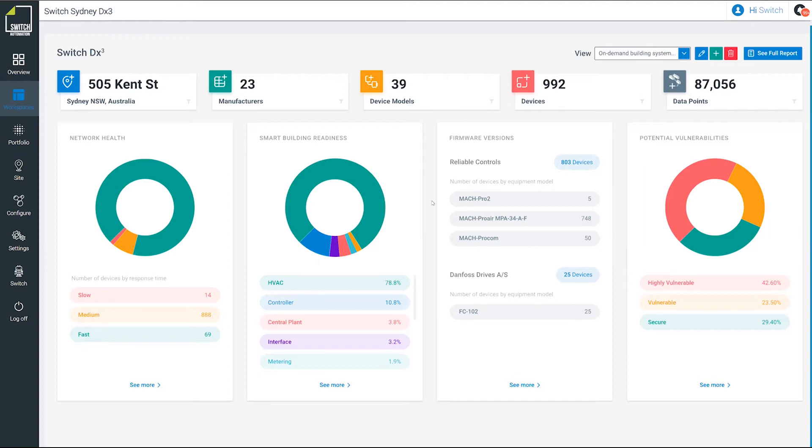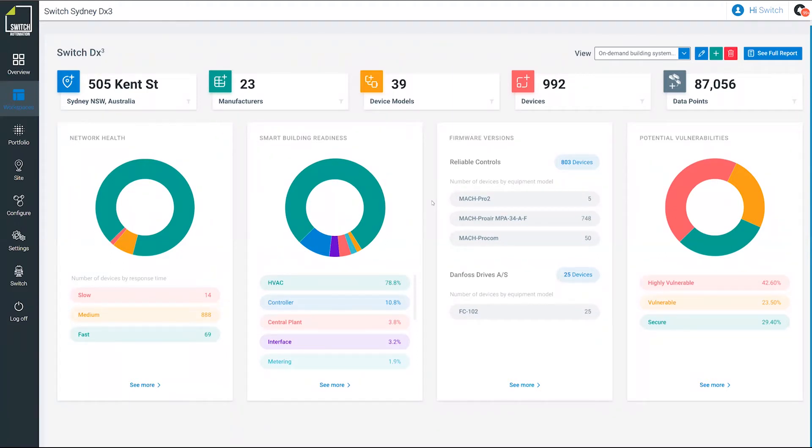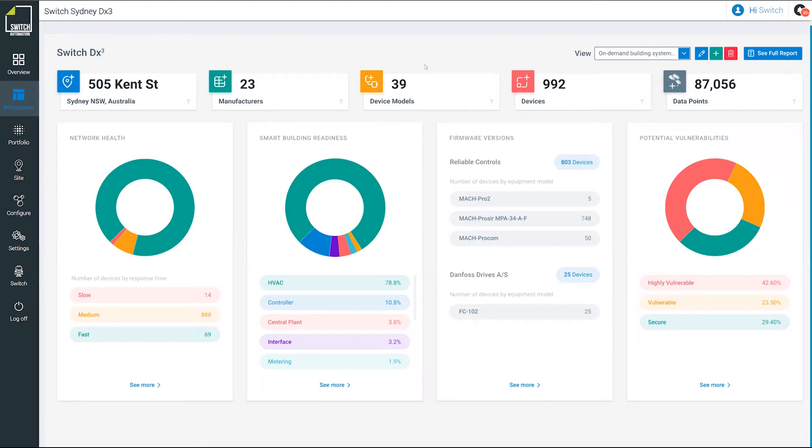Some of this functionality that I'm going to show you today is in the realms of IT people, and the operations teams don't necessarily see these sorts of things. You'll see at the top bar, this was a BACnet system network that we've discovered. We found a total of 87,056 sensor points on this network across 900 devices and manufacturers.